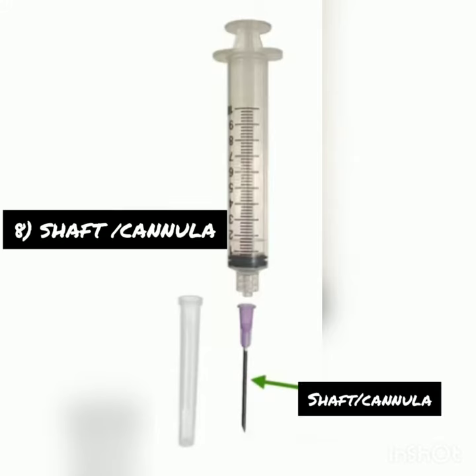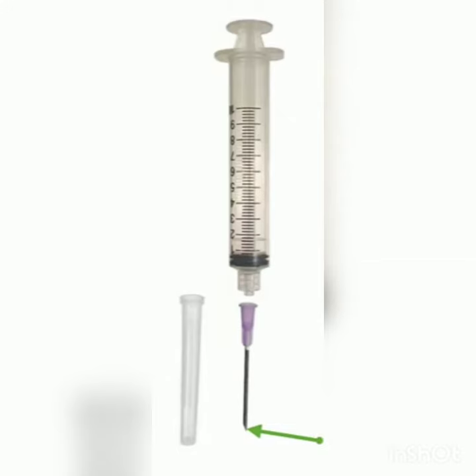Shaft or cannula: it is the long slender stem of the needle that is beveled at one end to form a point. The uppermost part is the bevel, which is the slanted part of the needle.